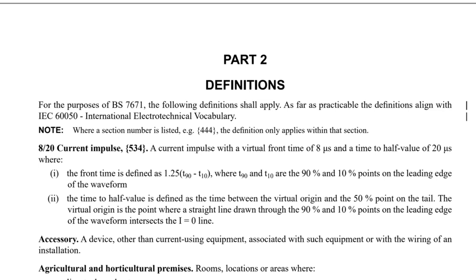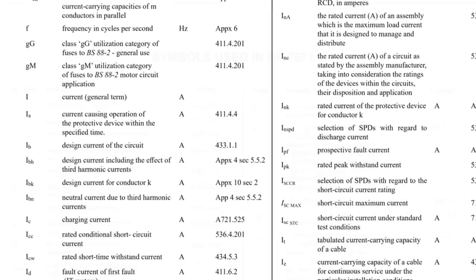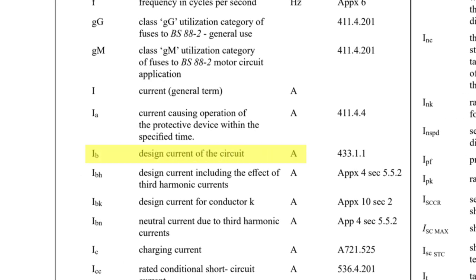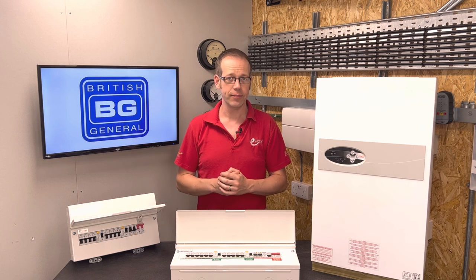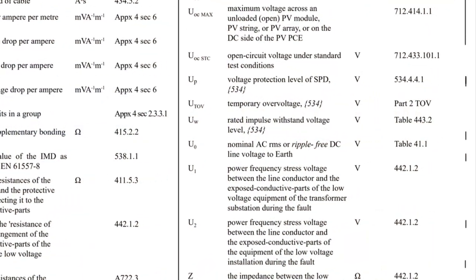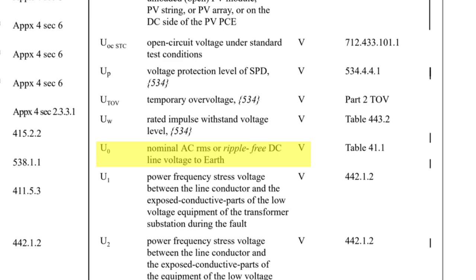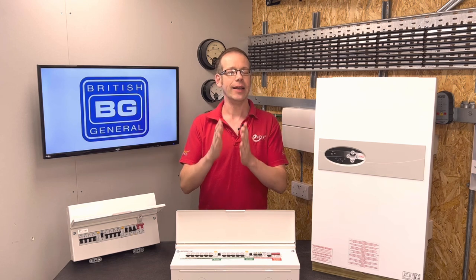Looking to BS 7671, we find the specific symbols we want to use in Part 2, which covers definitions and in particular the section on symbols used in BS 7671. Design current is measured in amps, as we'd expect, but the I — the mathematical symbol we use for current — is modified with a lowercase b in the subscript. Now we may be used to using V as the mathematical symbol in our calculations for Ohm's law at college, but the regs uses a capital U instead. This is because there are different kinds of voltage and it gets confusing using the same letter for the mathematical and the unit symbol. For our calculation, we need to use U with what looks like an O in the subscript, but is actually a zero. You'll often hear this referred to as UO, but it's technically U0.